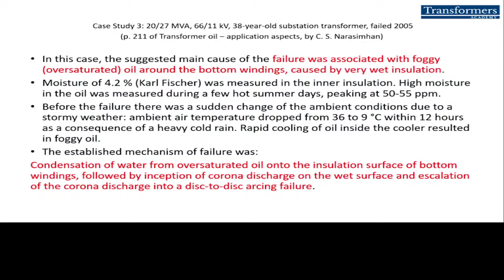The third case is again a case of oversaturation. A 20 by 27 MVA, 66 kV, 38-year-old transformer. Again, we are talking about old transformers where the insulation is wet. Under those conditions, one has to make sure that temperature fluctuations do not take place. Of course, certain temperature fluctuations are not in our hands, but overloading can certainly be taken care of.